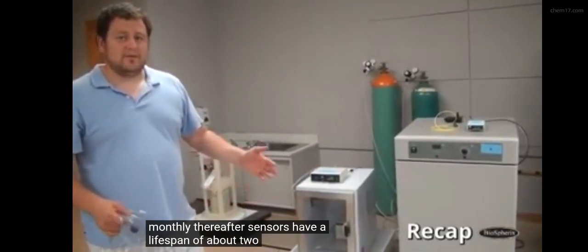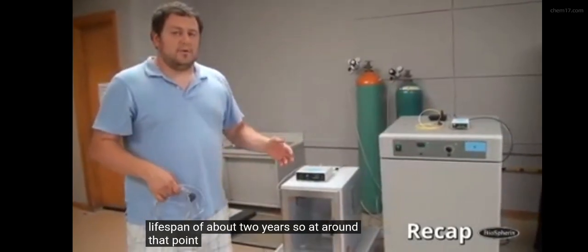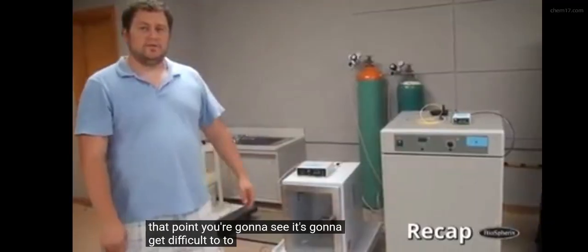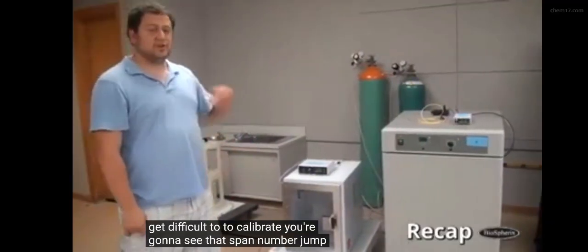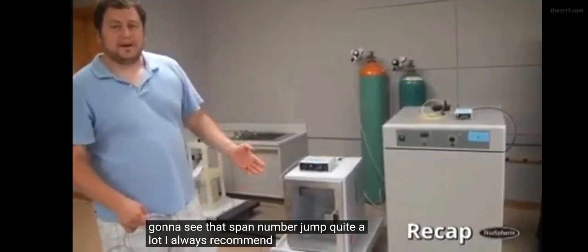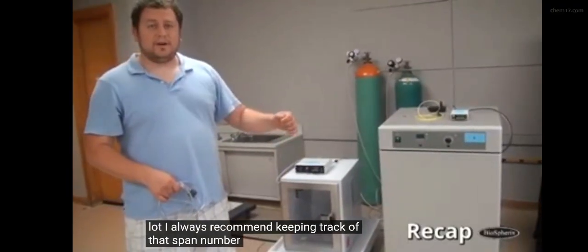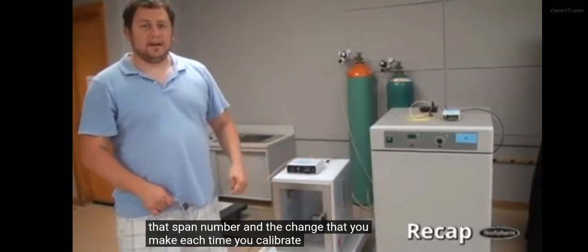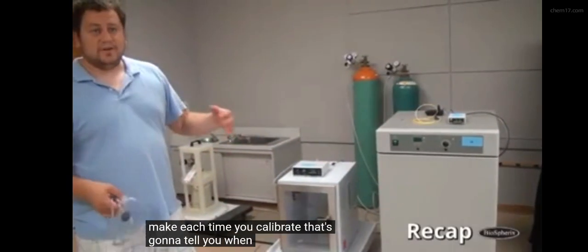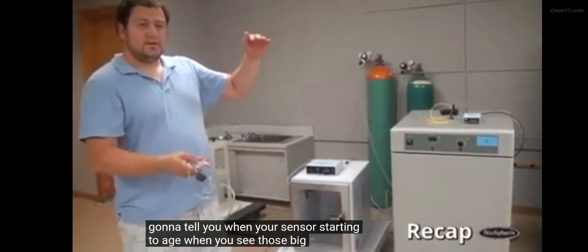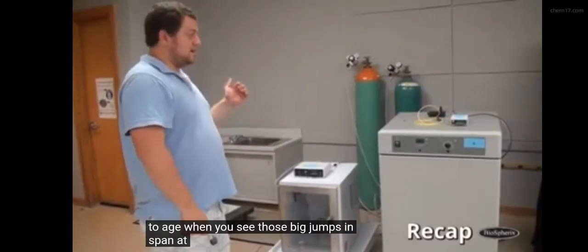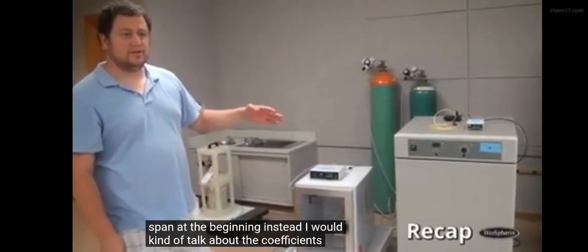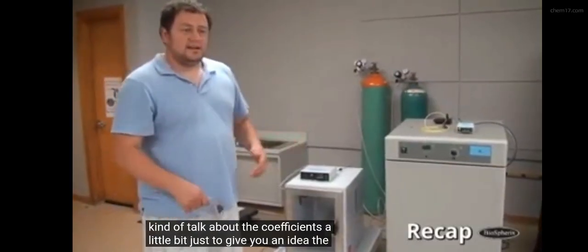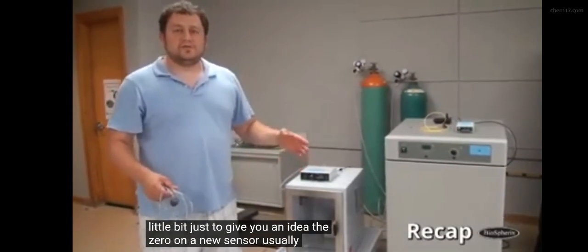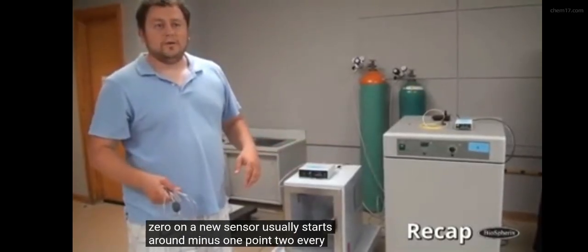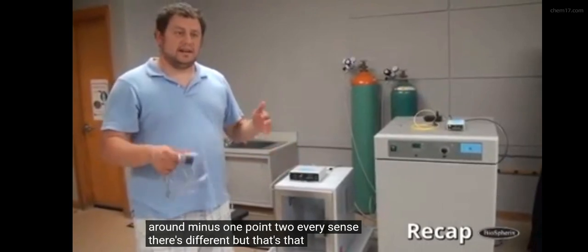Sensors have a lifespan of about 2 years, so at around that point, it's going to get difficult to calibrate. You're going to see that span number jump quite a lot. I always recommend keeping track of that span number and the change that you make each time you calibrate. That's going to tell you when your sensor's starting to age, when you see those big jumps in span. At the beginning I said I would talk about the coefficients a little bit, just to give you an idea. The zero on a new sensor usually starts around minus 1.2. Every sensor's different, but that gives you a good idea.